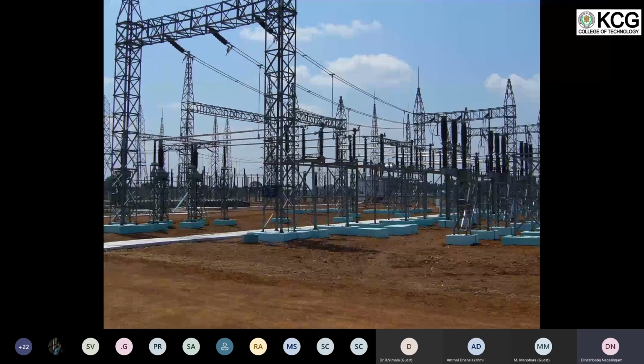A bus bar actually carries the total current of the substation, whereas a transmission line will carry only the current of that particular line. If we have 10 lines, one bus bar will carry the current of all the 10 lines. So it's a common node which carries all the current, as per the definition. A bus bar will have more conductors than a line. So if a line has 2 conductors, the bus bar will have 4 conductors. If a line has 1 conductor, the bus bar will have 2 conductors. In this comparison, we can easily identify which is a bus bar. So you can see the bus bar here.